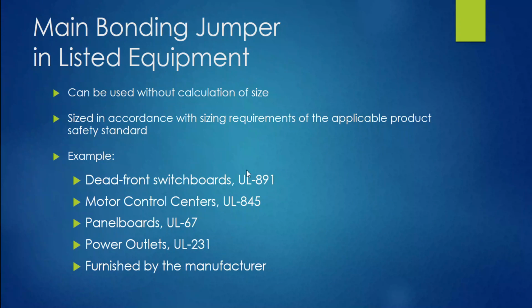So, the main bonding jumper in listed equipment. Okay, so let's say I buy listed equipment. If I buy a panel board, and in that panel board it has a green screw, or a Z strap, or whatever you want to call it, an actual bonding strap that is manufactured as part of its listing, in other words, it was evaluated with that product standard, then if you use that in the installation, I don't have to do anything.